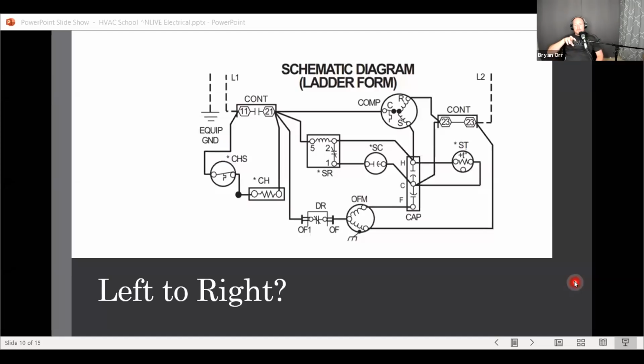This is how people do it when they work on big facilities. They're not being parts changers. They verify, checking against checking, making sure that it is that part before you condemn something and say that it's bad and throw it in the trash, right? Always double checking. And this is where even I use jumper wires more often than I even use meters in a lot of cases. It's very difficult for me to give a lot of examples of this because it happens in real life so often. The situations you run into vary so much.